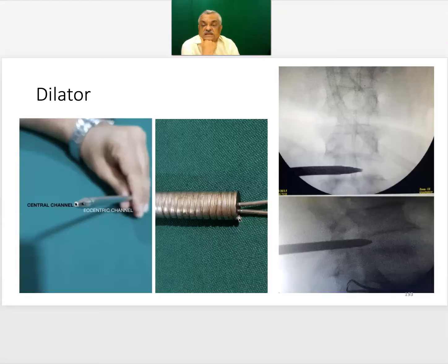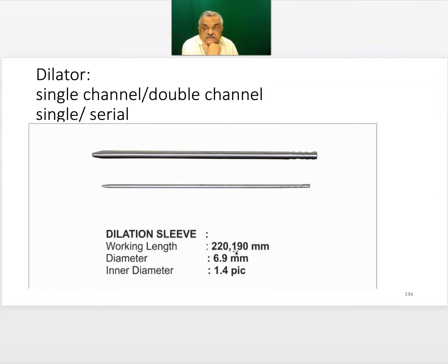Now the third instrument is the dilator, which is blunt in the tip. It has a central channel. It has an eccentric channel here. There are two channels as can be seen here. One is central, one is eccentric, and this is a blunt tip with a taper. My dilator has a taper of 15 millimeters. That is, from the tip to the big diameter area, this grows from 2 millimeters to 7 millimeters over 15 millimeters. So it is much more easy to use it. If you use a blunt dilator, it is very difficult to tap it inside the disc. Now dilator can be of single channel or double channel, and a single dilator, which is commonly used, or serial dilators are also used. The dilator is having a diameter of 6.9 and the inner is 1.4 through which the needle or the guide wire can go, the inner hole.